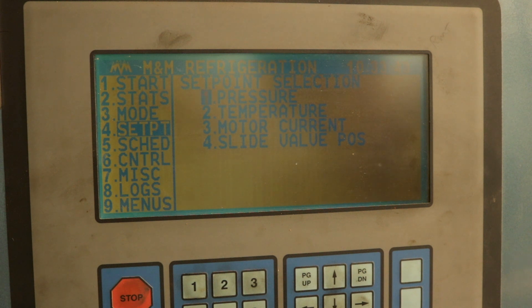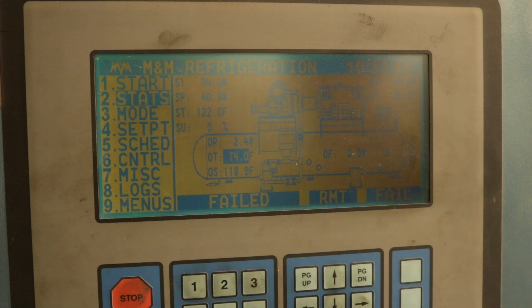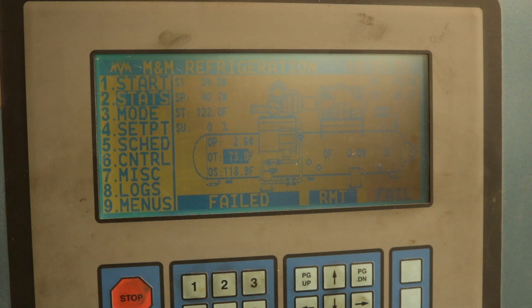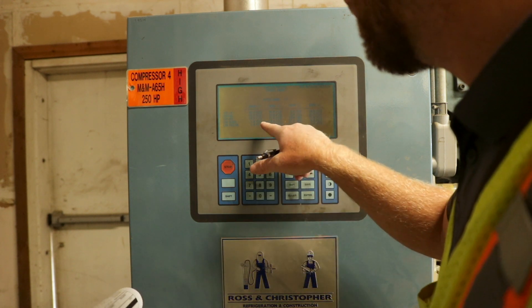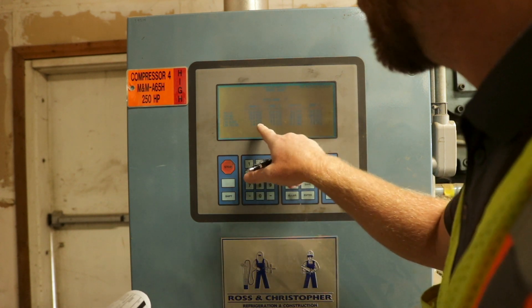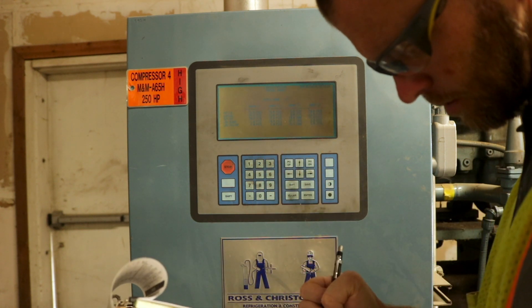Suction pressures can vary greatly depending on operating conditions. The inspector should consult with facility personnel to determine the normal suction pressure ranges. The discharge pressure for a high-stage compressor is typically between 120 and 180 psig. This compressor is operating at 140 psig, which is acceptable.